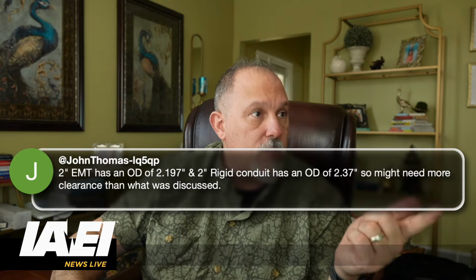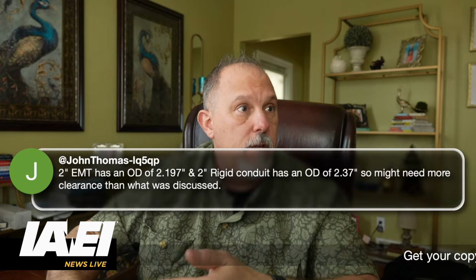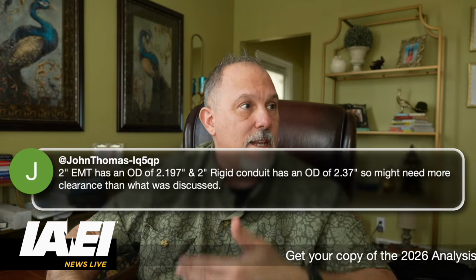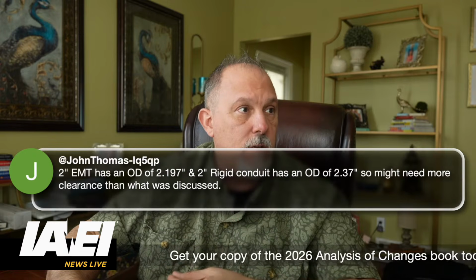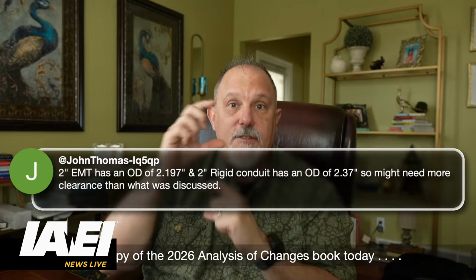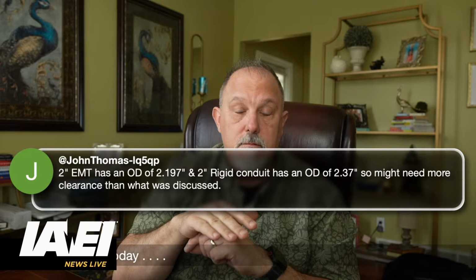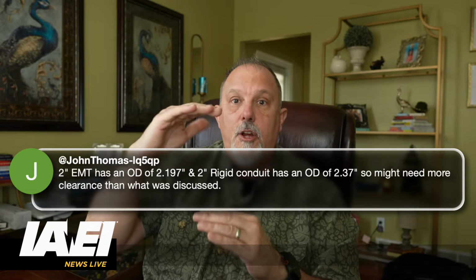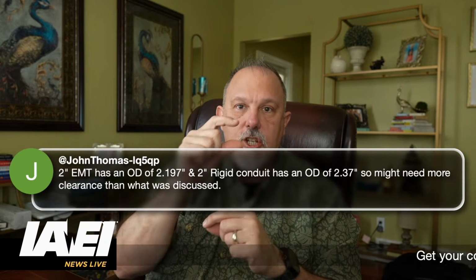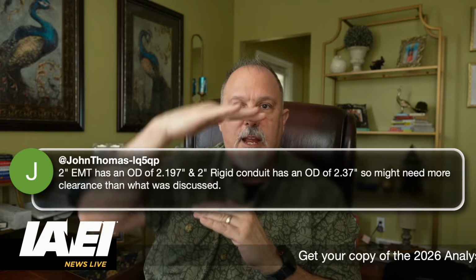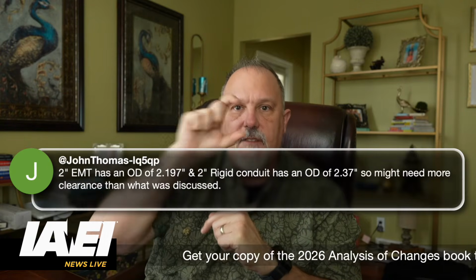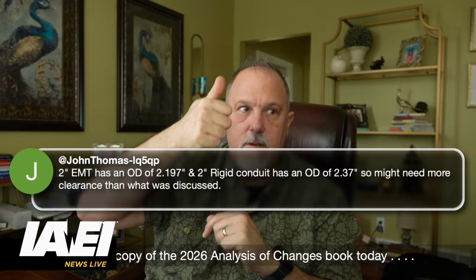Wiring methods and materials installed under roof decking shall be installed to maintain not less than 1.5 inches of separation. So I would argue 2 inches on top would be all that you need. If I have 1 inch conduit and I have 2 inches and I push that conduit all the way to the bottom, I've got 2 inches of concrete on the top. That's all I need. And it's encased.